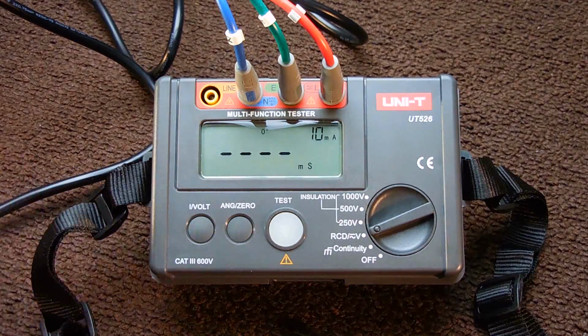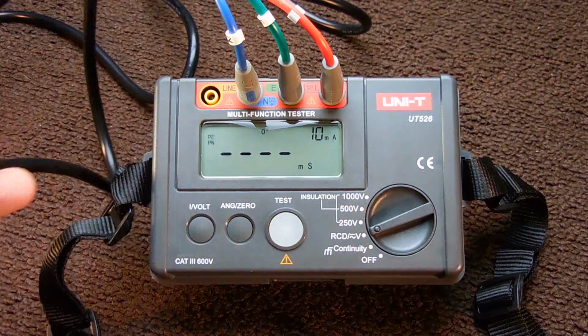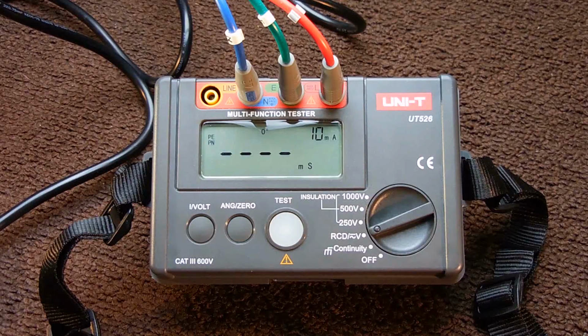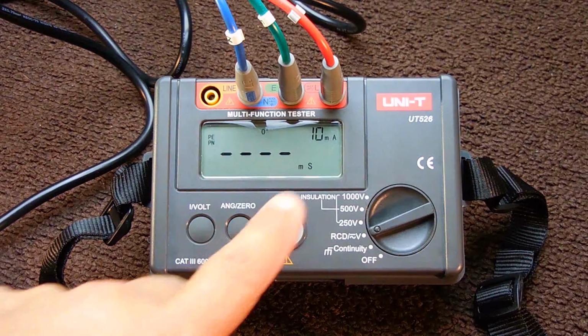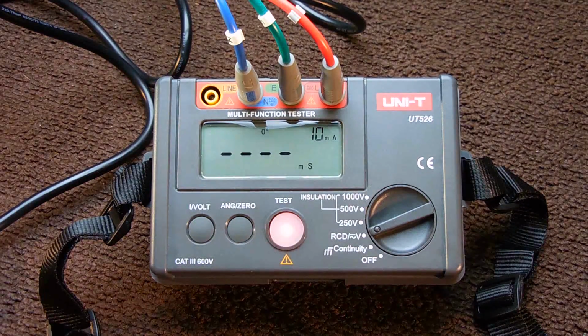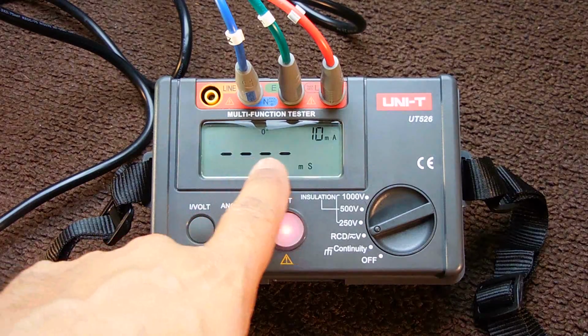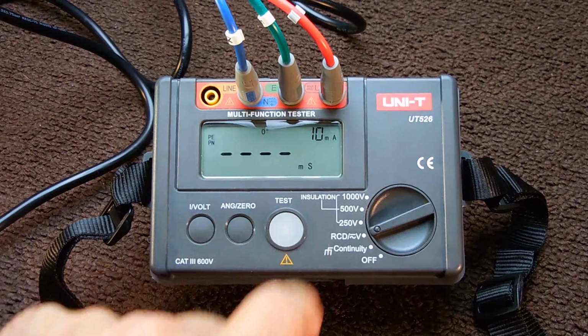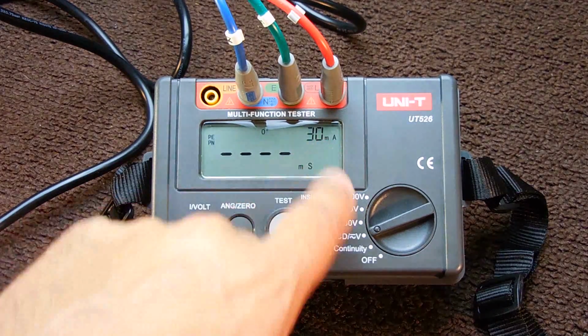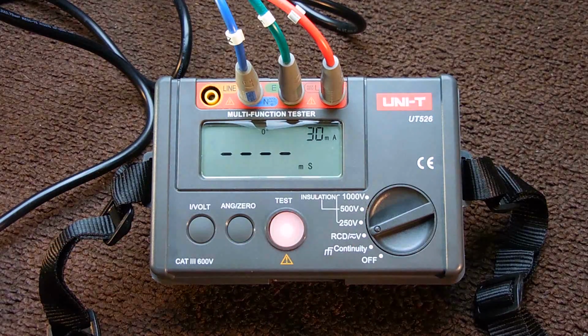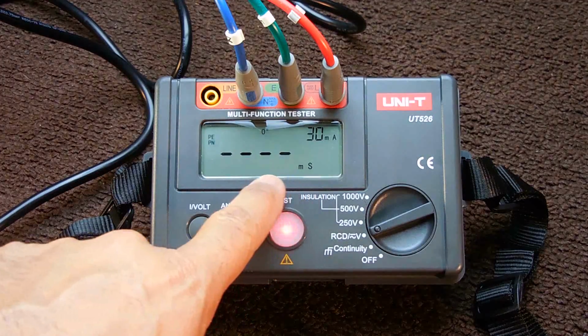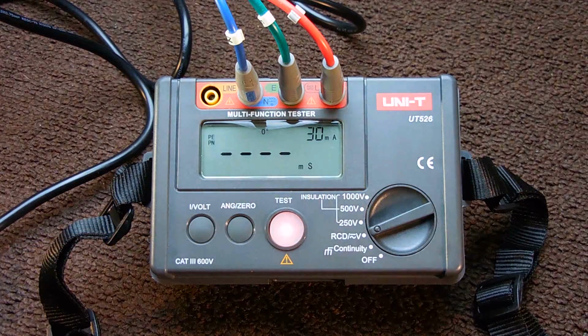Once you have it set, you plug this end right here into an RCD protected branch circuit, push the test button, and then you wait to see if it trips. If it does not trip, then you're going to turn it off. You're going to increase to 30 milliamps, push it again. When the circuit breaker trips, it's going to display how many milliseconds it took for you to trip that breaker. It's a useful feature, but one that I do not use.